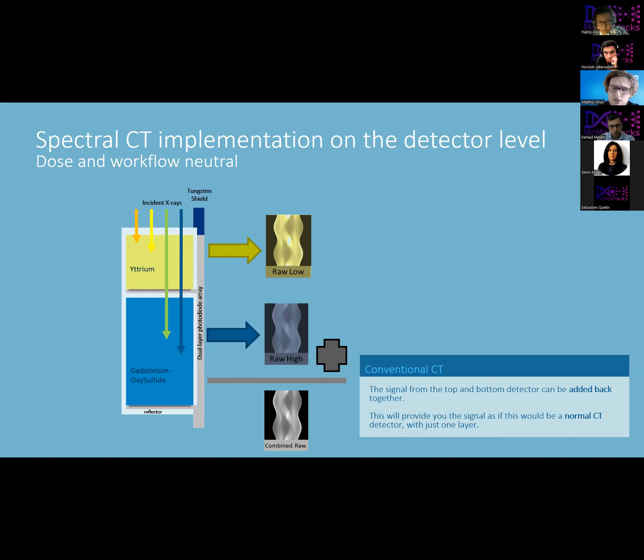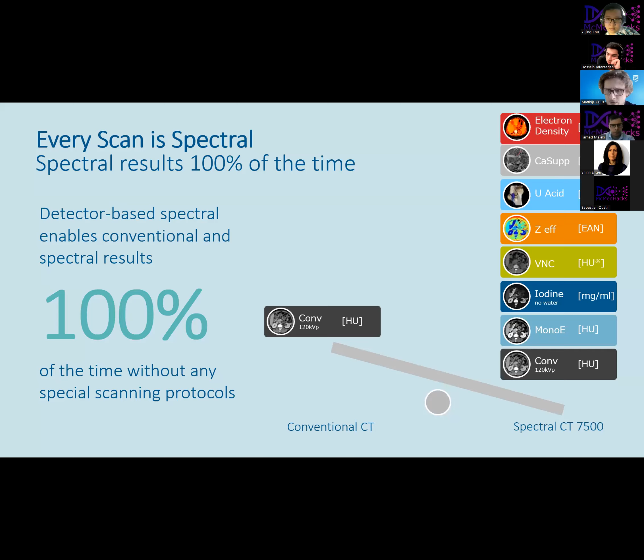So normally what we get from a CT scanner, for instance if we scan at 120 kilovolt peak, is a Hounsfield unit image. But if you do spectral CT, you get a whole lot of different other results. And I'll go into some of them, trying to explain a little bit what they are and how they are being used. So what we get is a monoenergetic image. And these are represented not in kilovolt peak, but in kilo electron volts, so keV instead of kVp.